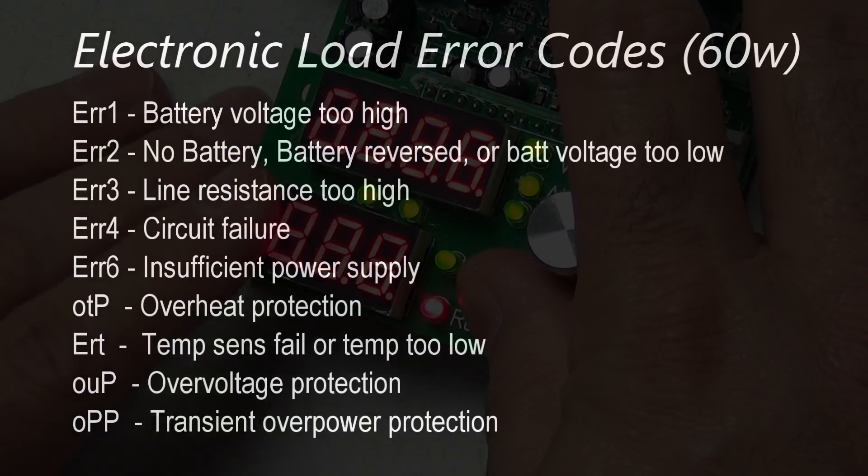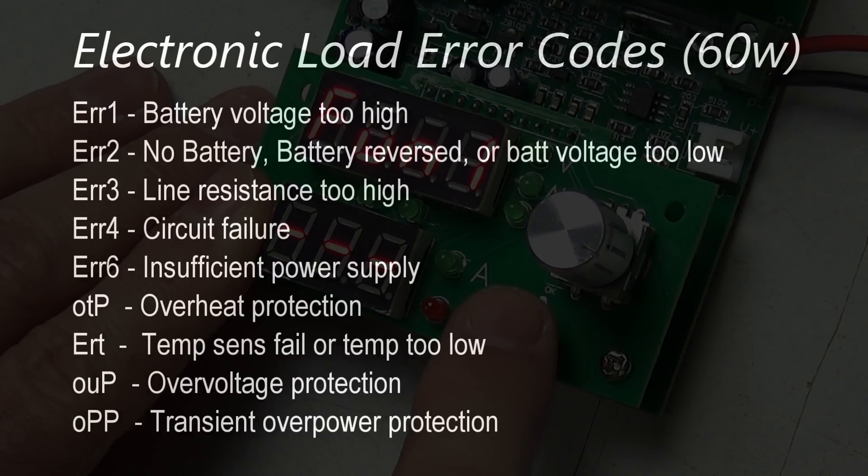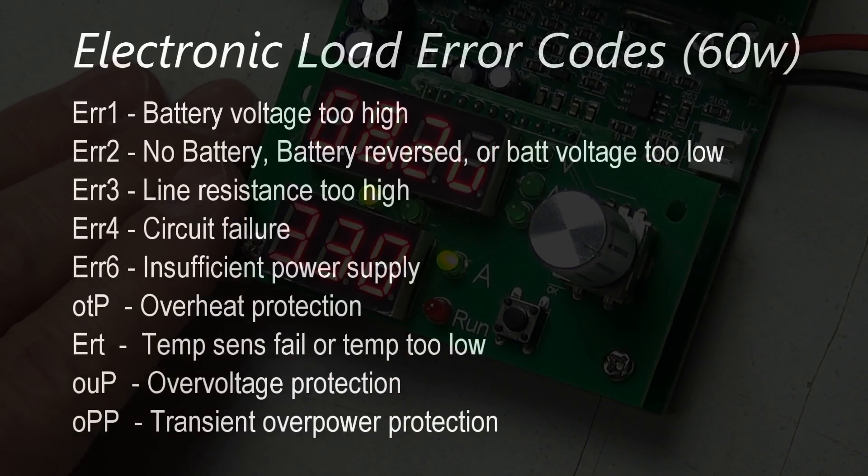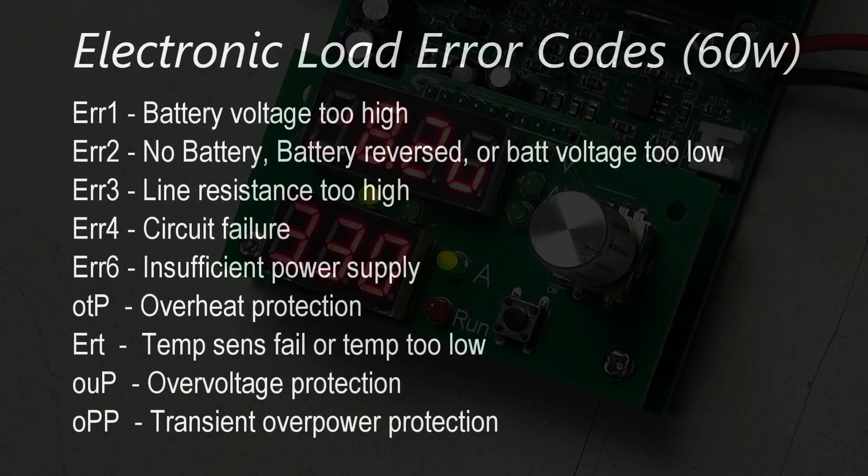Error three is line resistance is too high. I've actually run into this error trying to connect a battery through very thin wires to the electronic load for testing and the current was set too high on the device and it simply gave an error code, so I needed to use thicker wire and that fixed the problem. Error four is circuit failure, I haven't come across that error yet.